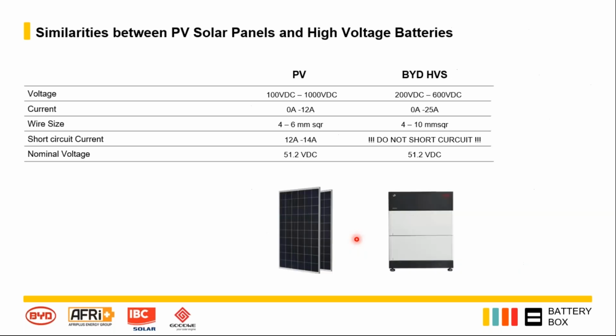With regards to how to familiarize yourself with high voltage batteries, I'd just like to compare them to something that's very similar, which is your photovoltaic solar panels. So here we've got a comparison between a high voltage battery and photovoltaics. And here we can see the voltage of your photovoltaics. You typically have anywhere between 100 and 1,000 volts. And your BYD HVS batteries are between 200 and about 600 at maximum. The max is 500 nominal, but there is sometimes where it goes up to 550. So your voltages are fairly similar.